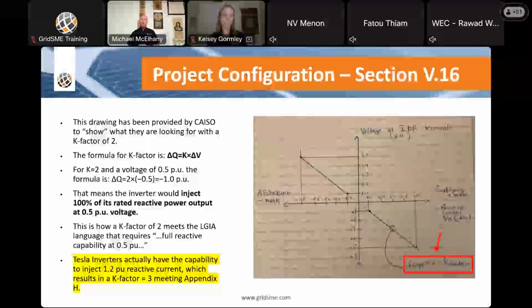Once you get below 0.9 per unit, you need to start moving and injecting proportionally, which is what it says in Appendix H, until you get to 0.5, where you've hit the full reactive capability of the plant. So in simple terms, it's basically a slope.